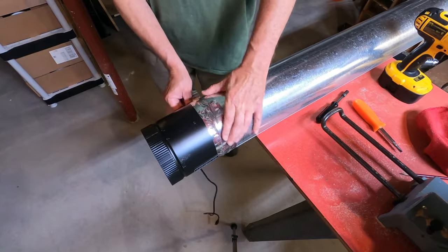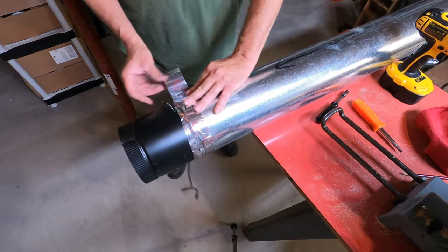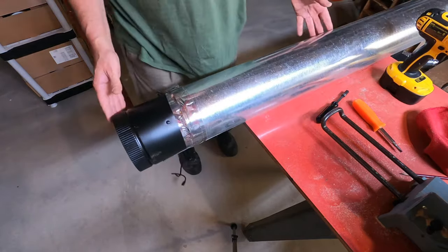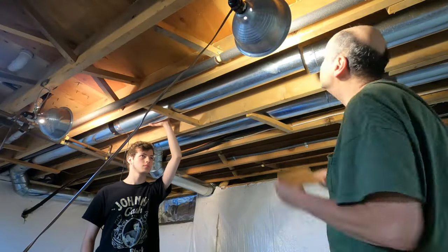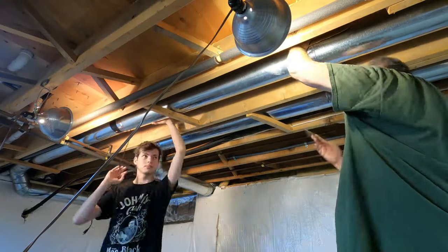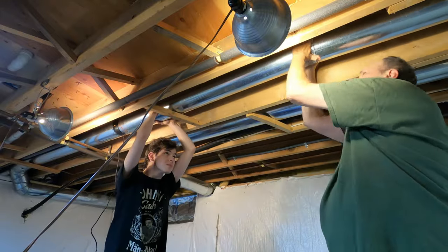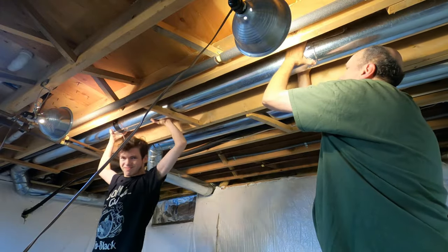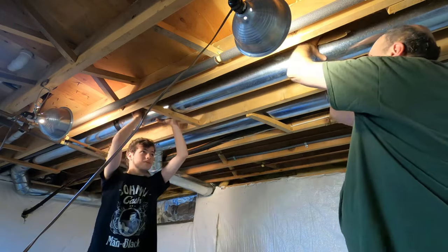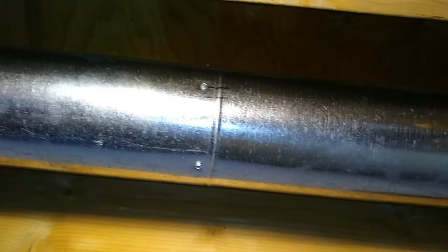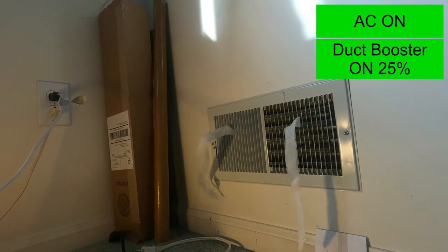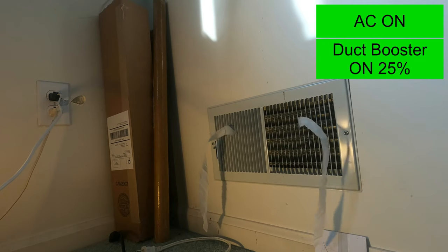Another frequently discussed question was, does this duct booster pull air from other rooms? Some of the commenters theorized that this booster will take, rob, pirate, or steal air from the other ducts. I didn't add a new duct to this system. The fact that the faulty duct has always been there and has always been short on airflow can't be ignored. This problem resulted from a duct run that was poorly designed in the first place. It flowed almost no air, while the other ducts didn't have this problem.